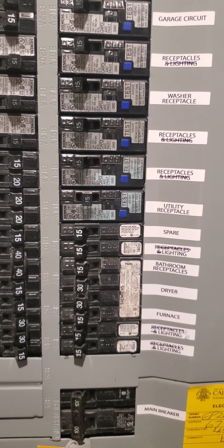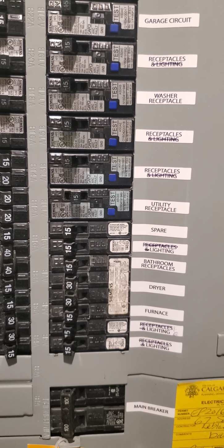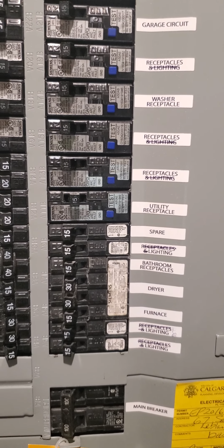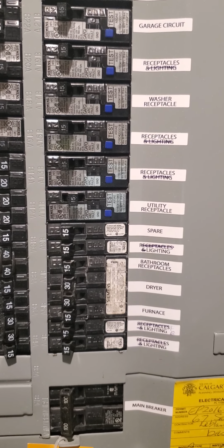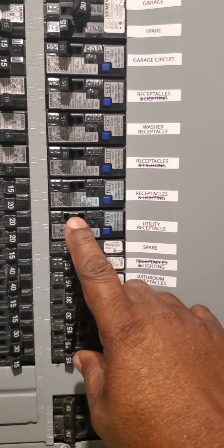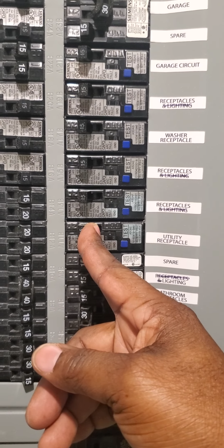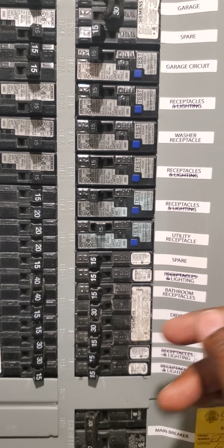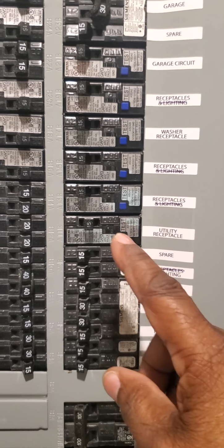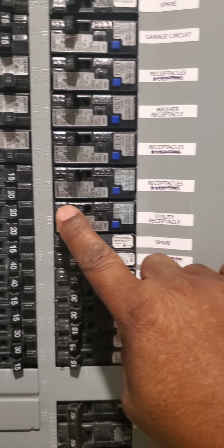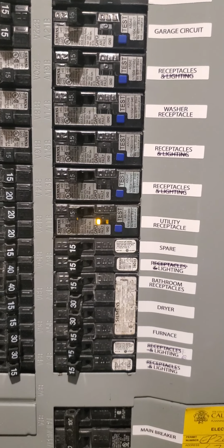So I went and I searched the circuit, the wires, and I found out what the issue was. So I repaired that issue. So now we can go ahead and reset this breaker. So first of all, we're gonna come here and we're gonna not turn it on, because as I said, if you turn it on and you let it go, it's gonna come back to the trip position, which is in the middle. So we're gonna turn it off and then we're gonna turn it back on, and let us see if it's gonna trip again.